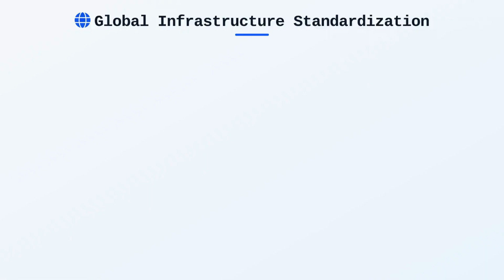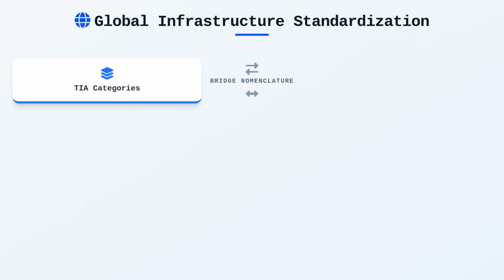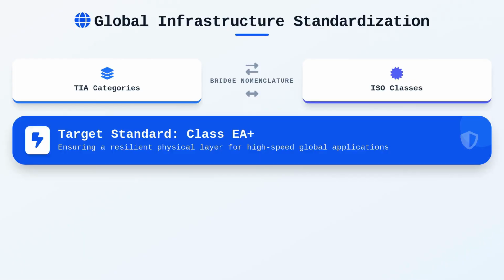Ultimately, the goal is to create a seamless infrastructure that ignores geographic borders, yet respects local standards. Your role as a designer involves bridging the nomenclature between TIA categories and ISO classes, while ensuring that your testing equipment is configured to verify the correct international standard. By standardizing on Class EA or higher, you provide a resilient physical layer capable of supporting current and future high-speed applications regardless of the global location.